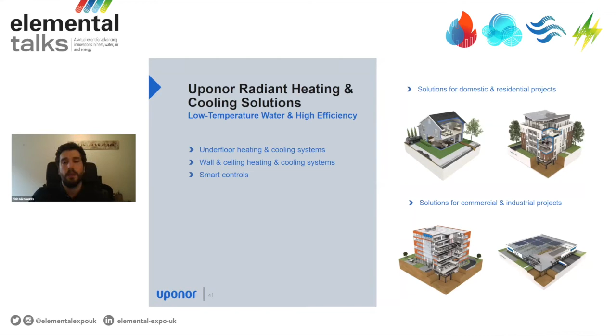So we will start with the most widely known application of a radiant solution, which is the underfloor heating systems, and more specifically the systems that are mainly applicable in domestic and residential applications. So Uponor's Minitec system is a prime example of a low-profile underfloor heating system. It is ideal for renovation projects as it has a minimum buildup of 15 millimeters, including the 10 mil pipe. The system comprises the Minitec panel, which is a castellated panel with a sticky lower surface. The adhesive on the lower surface is used in order to attach the panel on top of an existing solid floor, rigid insulation, or a timber floor overboard.